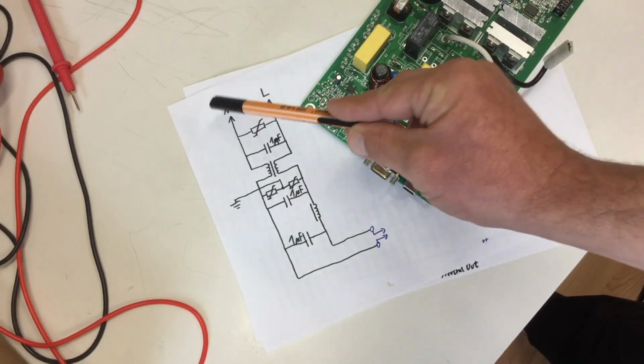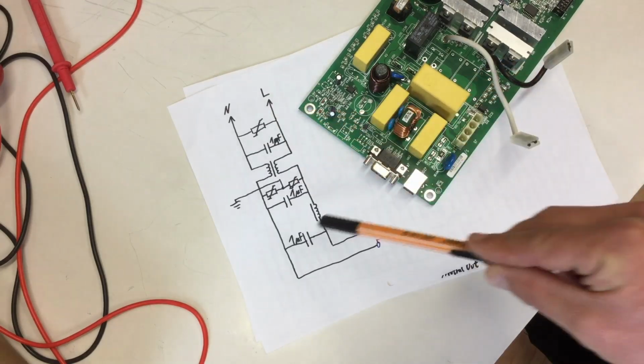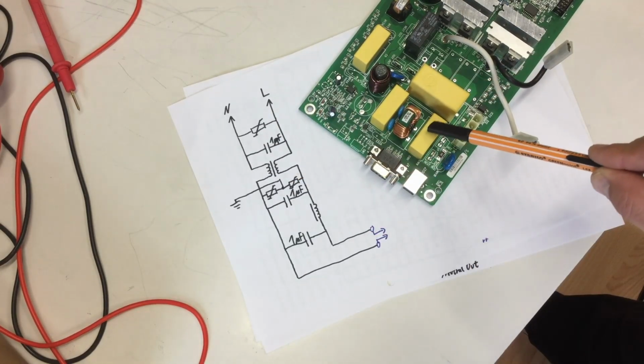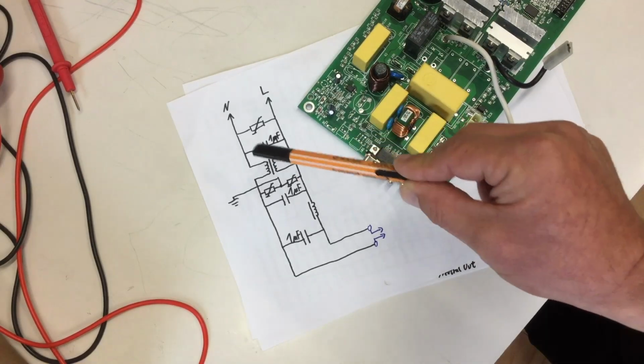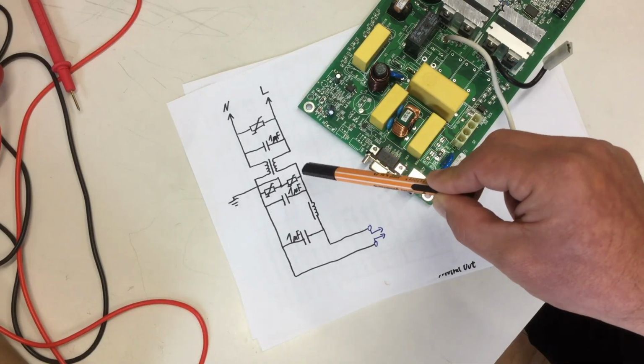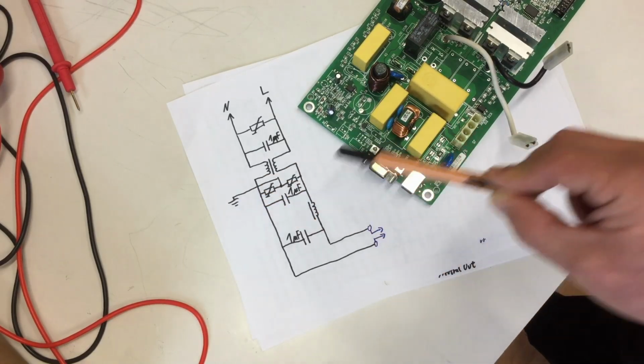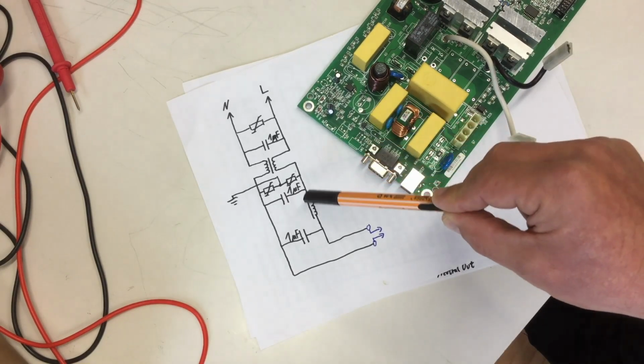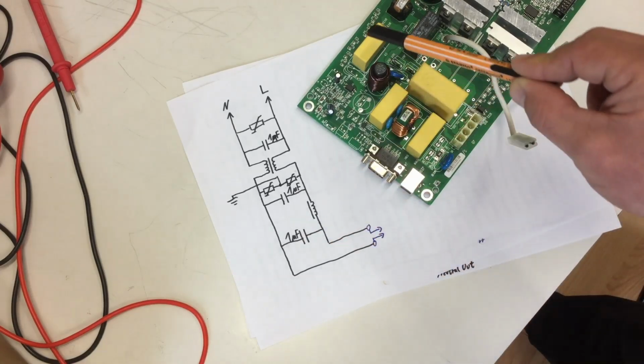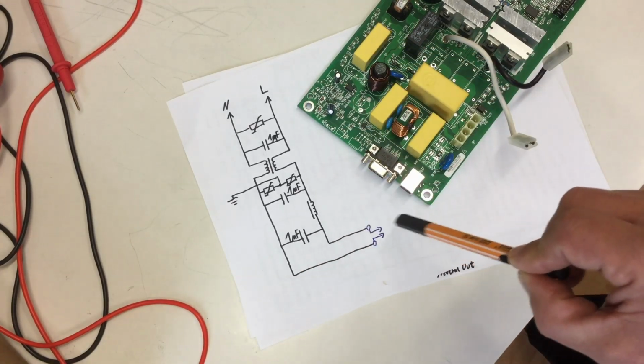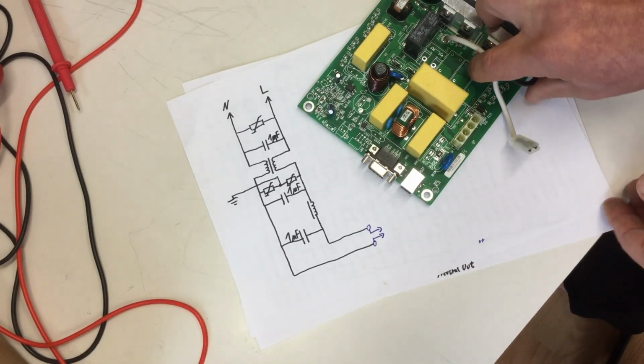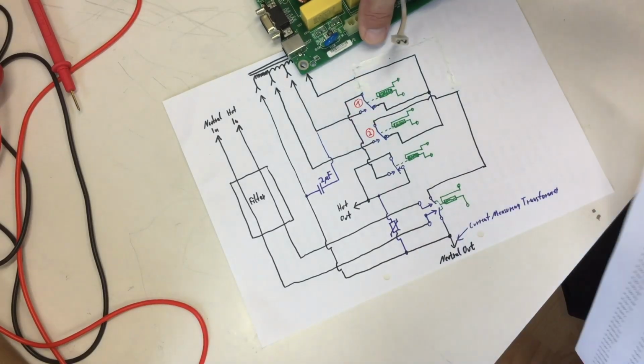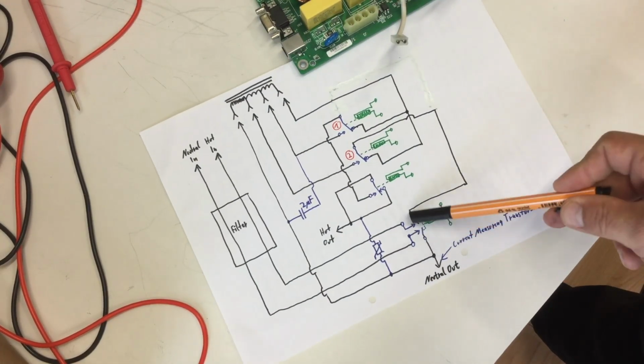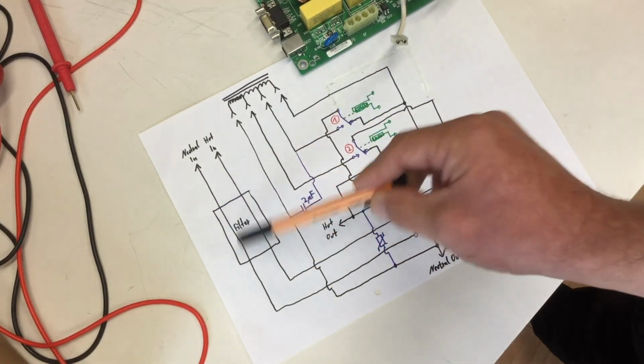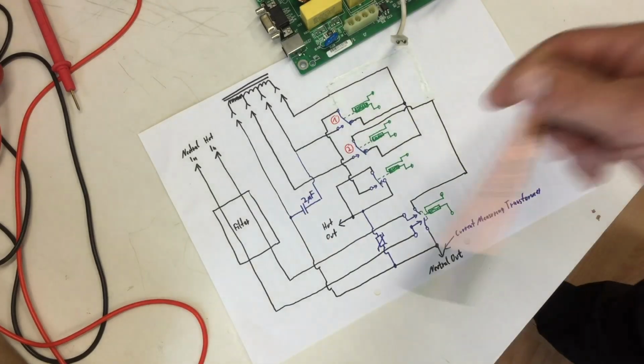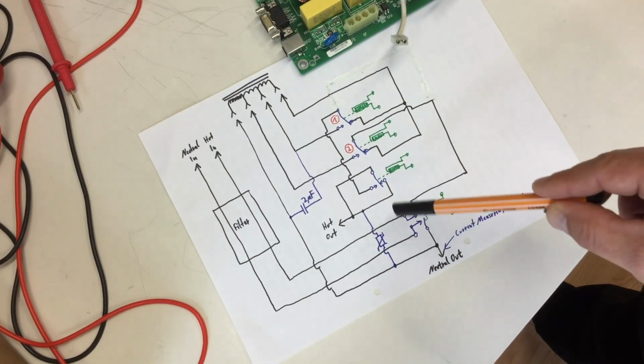Neutral, live, or how they call it, neutral and hot, comes in. There's one big MOV, then comes a big 1 microfarad capacitor, the common mode choke, 2 more MOVs between live and neutral and ground, another 1 microfarad capacitor, the inductor, and then another 1 microfarad capacitor, and that all goes down to another sheet, to that input relay, which can switch on and off all the stuff, both live and neutral - that's the filter basically.